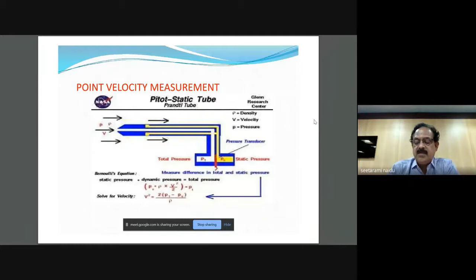You have to have a manhole to access the interior of the penstock, and this is usually recommended for penstock diameters above 1 meter. What we have is a minimum of 13 current meters, 1 at the center and 3 each on the 4 arms of the cross. It is called a cross arm. We have to have a small flat connected inside the penstock and mount the current meters on these cross arms. Ott, Germany-type current meters were there in CWC. We are extensively using this for flow measurement, but it is a very tedious task.